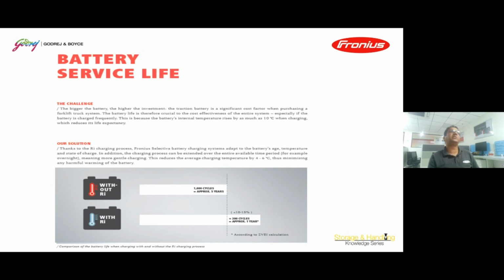Second important factor is battery service life. How will the battery service life increase? Typically when we do charging with the conventional process, it's a predefined charging current, so the battery and charger have no communication between them. Whenever the battery is 80% discharged, the conventional charger, which is predefined, starts charging with the decided current. No communication. They don't understand each other, they don't communicate. Here, the charger is communicating through data, taking data from the battery and appropriately converting it into the current required against the resistance.